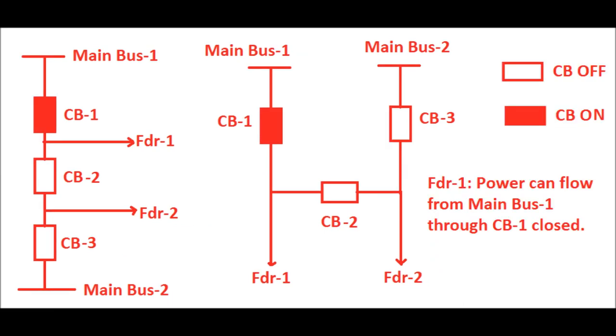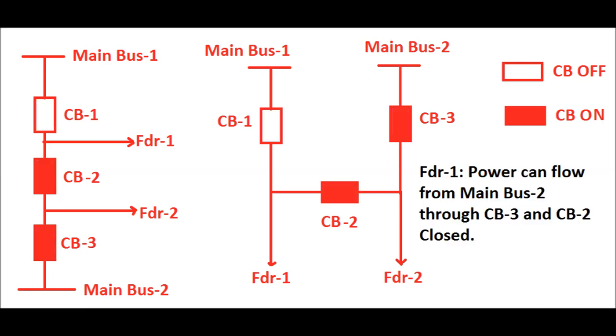How does feeder 1 get power? There are two paths: one via main bus 1 and another via main bus 2. Via main bus 1, feeder 1 can receive power through circuit breaker CB1, which is towards main bus 1, being closed. Again, feeder 1 can receive power through main bus 2 via CB3 — the circuit breaker towards the main bus 2 side — and the middle CB, that is CB2, being closed.